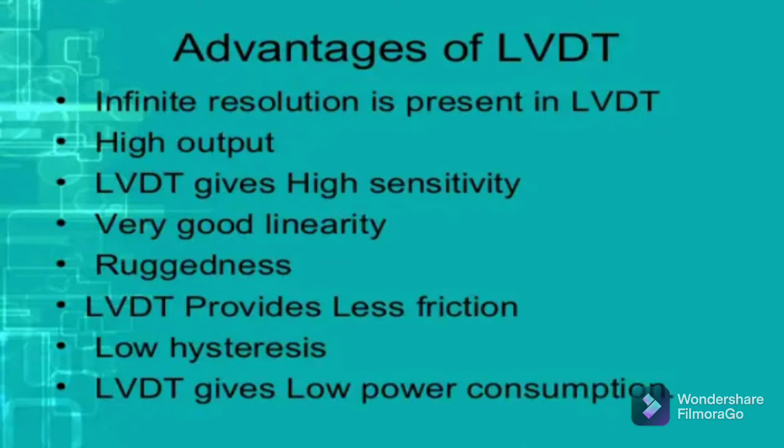This is especially useful when the core is loaded with a spring. The sixth advantage is low power consumption — LVDT consumes very low power, approximately one watt during operation. The seventh advantage is direct conversion to electrical signal — they convert linear displacement directly to the corresponding electrical voltage signal, which is easy to process further. The last advantage is fast dynamic response — due to the absence of friction, its dynamic response becomes very fast to changes in core position.